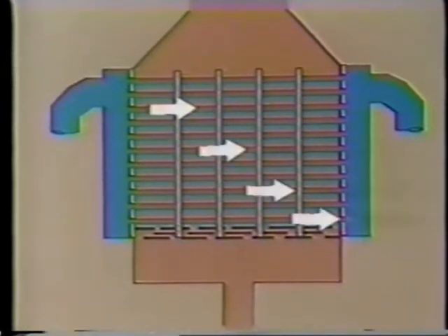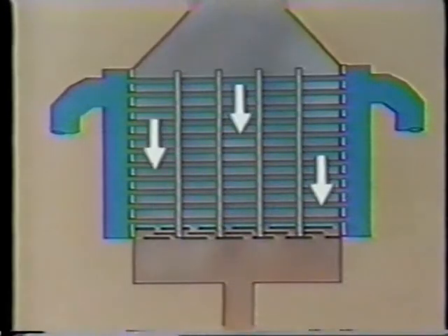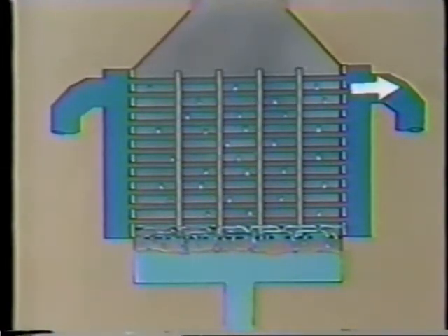During normal operation, cool circulating water enters the condenser through the circulating water inlet. The water flows through the inlet water box and then through the tubes. At the same time, steam enters through the steam inlet and flows around the tubes. When steam comes in contact with the surface of the cool tubes, its latent heat is transferred to the circulating water flowing through the tubes. This causes two things to happen. Steam condenses on the sides of the tubes, and circulating water is heated. The heated circulating water flows through the outlet water box and into the outlet piping.